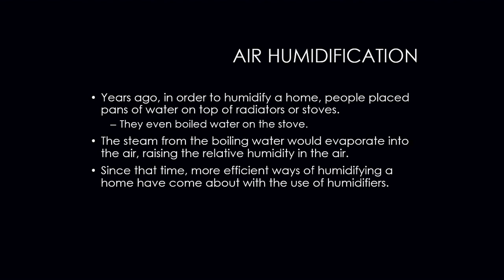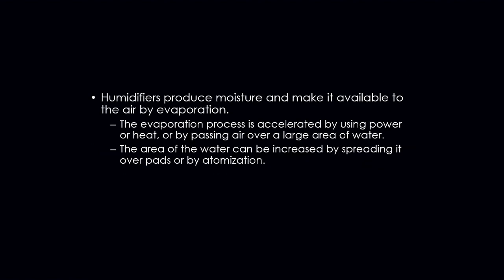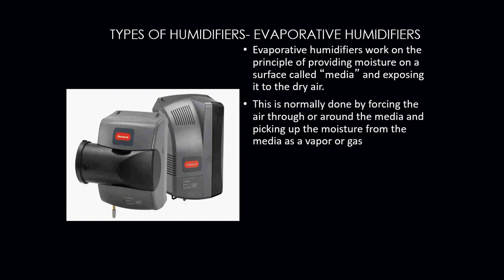Okay, so the steam from the water would boil and evaporate into the air, raising the relative humidity. And since that time we've had much better technology, and now we have equipment we can put in to control this without having to constantly put on a pot of water to humidify a space. So we have what we call humidifiers now. Humidifiers produce moisture and make it available to the air by evaporation. The evaporation process is accelerated by using power or heat, or by by passing air over a large area of water. The area of the water can be increased by spreading it over a pad or by simply atomizing the water. And here's an example of your types of humidifier.